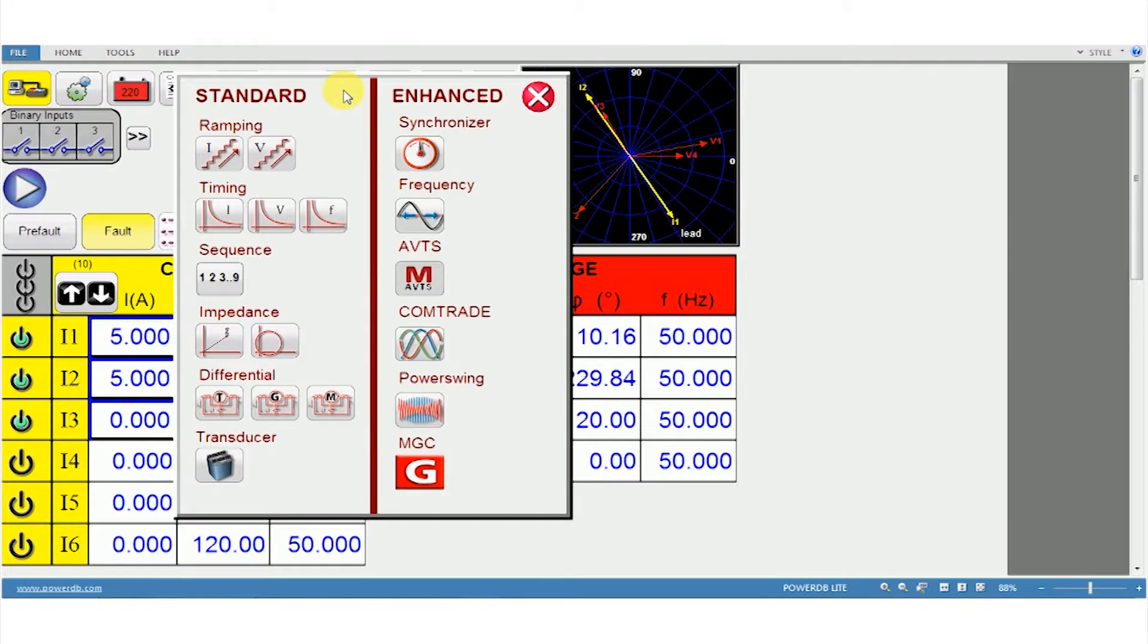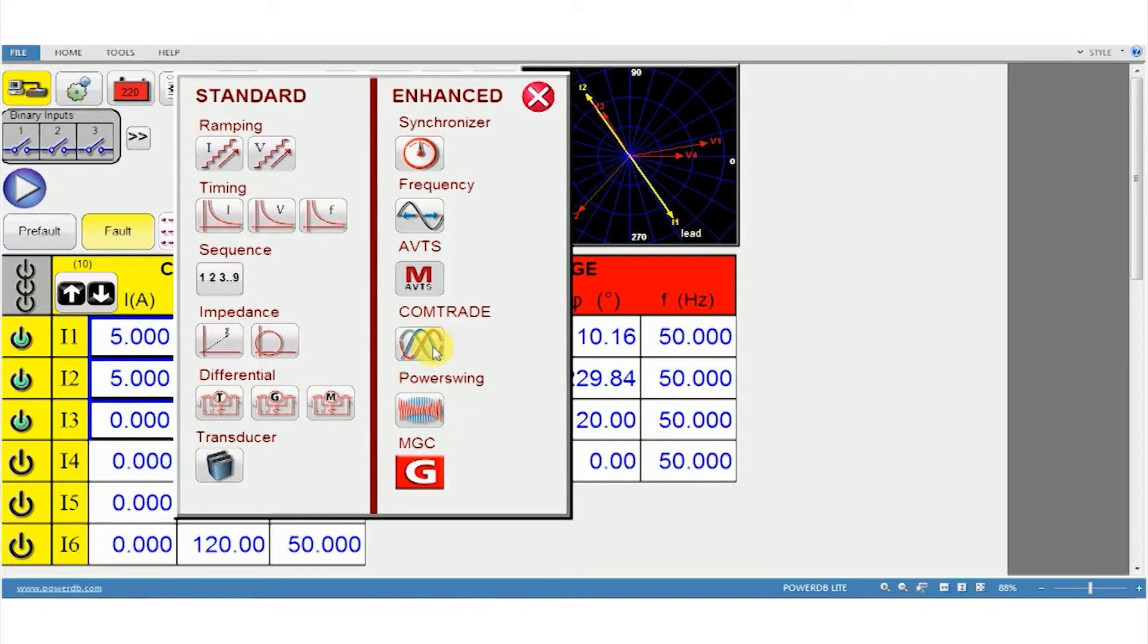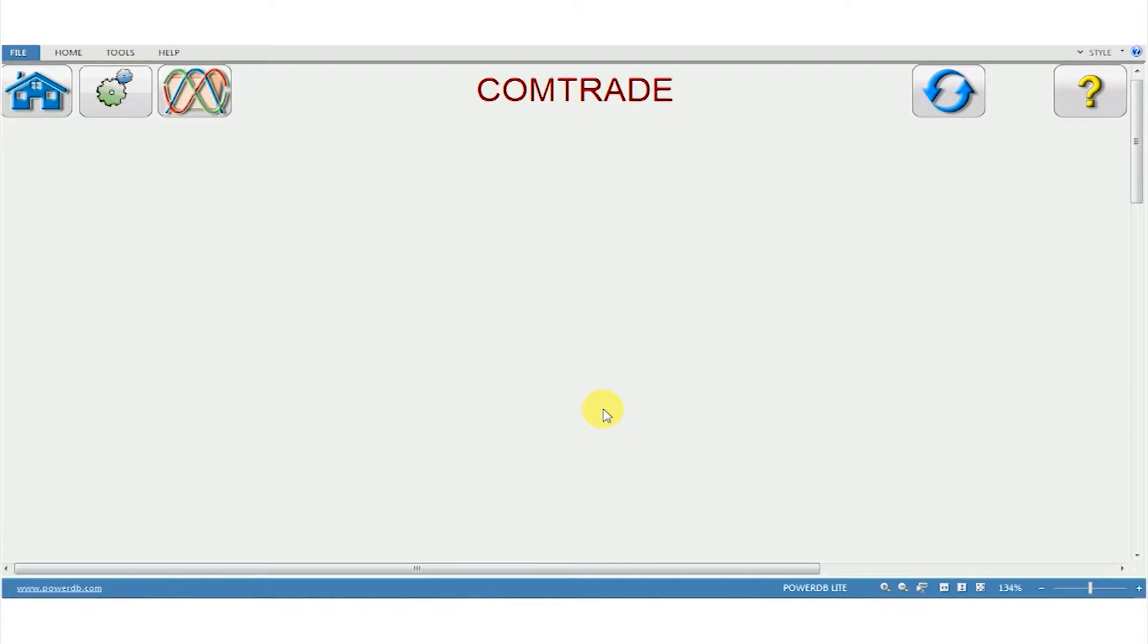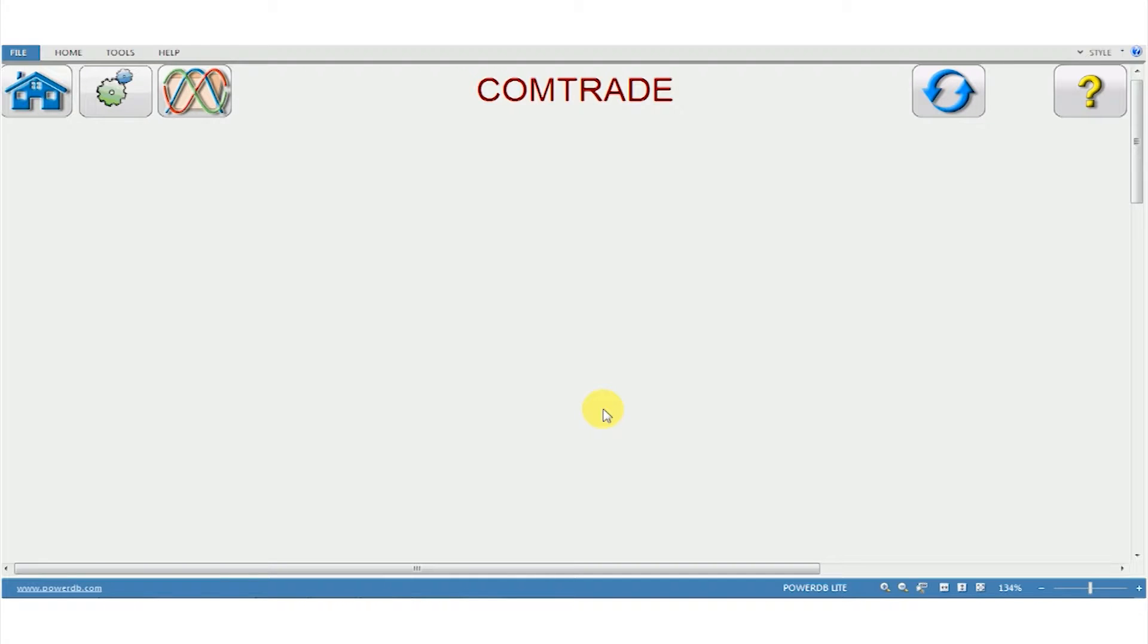In this software we'll use the test module called Comtrade. When I click on this a new window opens. I've currently connected a test kit to ABB REL670 relay and I have two oscillograph files from a different make relay, the GE D60 and D30 relay, which has tripped at site for different fault locations. I'm going to import to playback and verify the results.